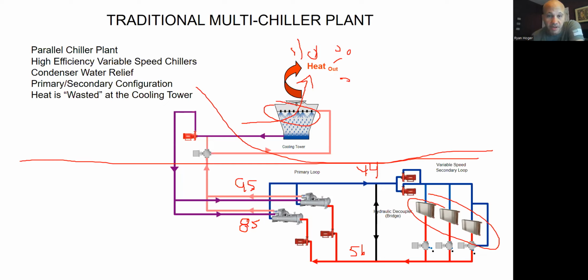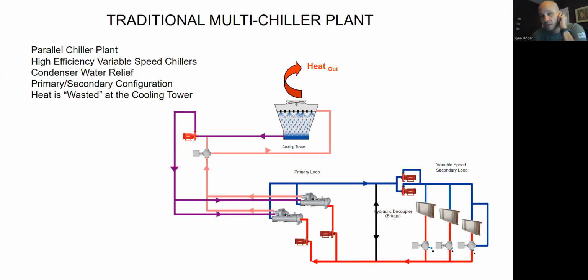All right, so what that guy does is take my 95-degree water, evaporatively cools it, and sends me 85-degree water back, where I can now use the refrigeration cycle in one of the chillers to keep dumping more heat into it. All right, hopefully this is making sense. So what the interesting thing is, is that I have chillers like this. I'm saying the industry has chillers like this running all over the world, and they're running in all seasons. So like I told you guys before, I live in Illinois, only like an hour from Chicago. In Chicago, there are hundreds of buildings that have chillers like this with a cooling tower that are running this cooling tower in the middle of winter when it's like 0 degrees outside, right?